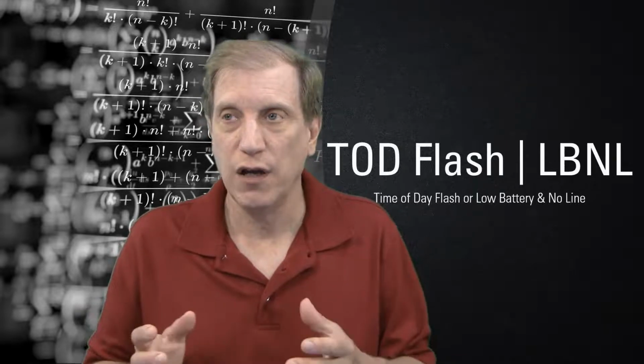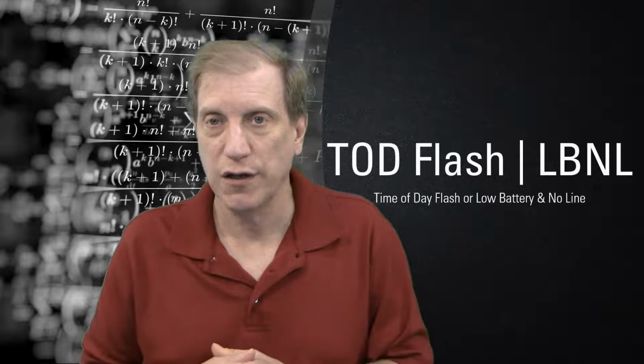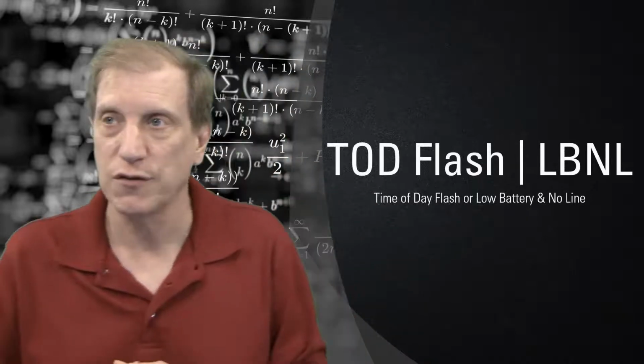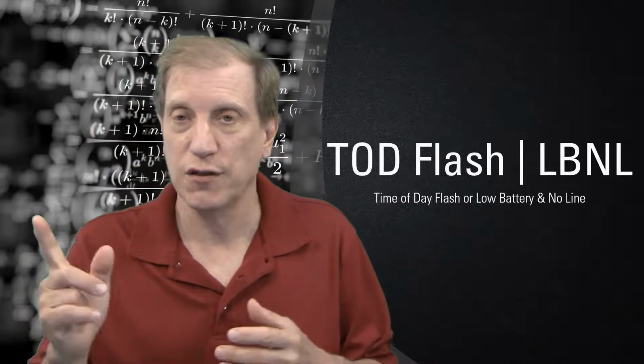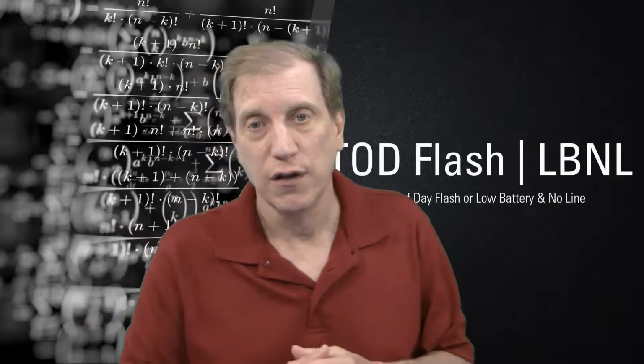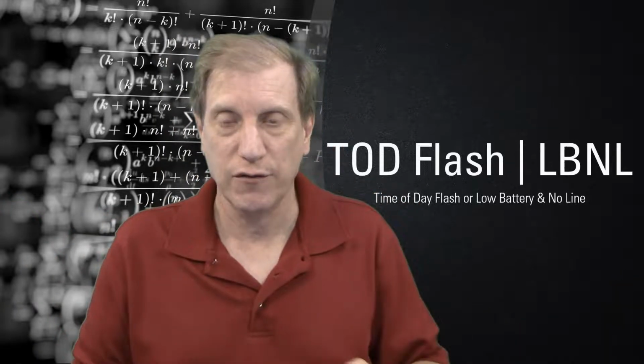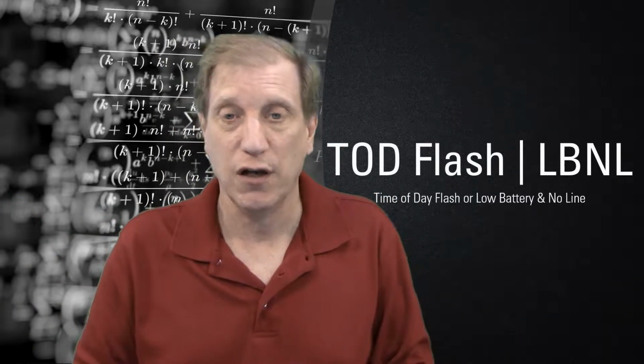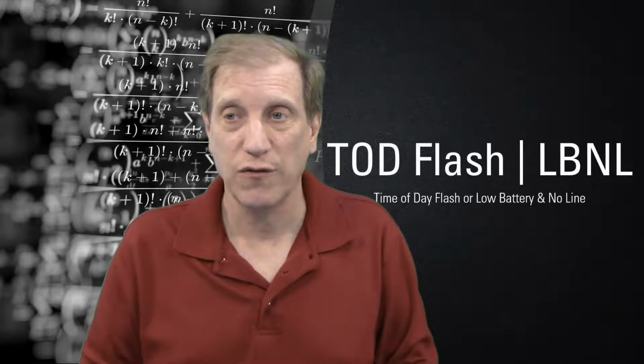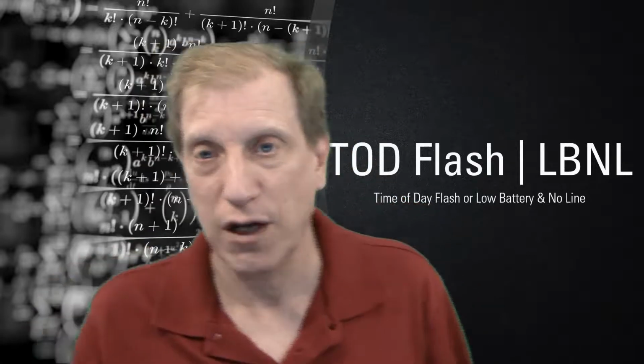So how do you do that? Well, you can do it with a custom data equation. Legacy product can't do it, but you can do it with this. But the other condition is low battery, no line. What if, not during the middle of the night, it's during the middle of the day and you happen to have a long outage? You may still want it to go to flash when you hit that 40% or lower level. So we're going to bring both of those in, and this time we're going to use some and or statements to make this all happen.